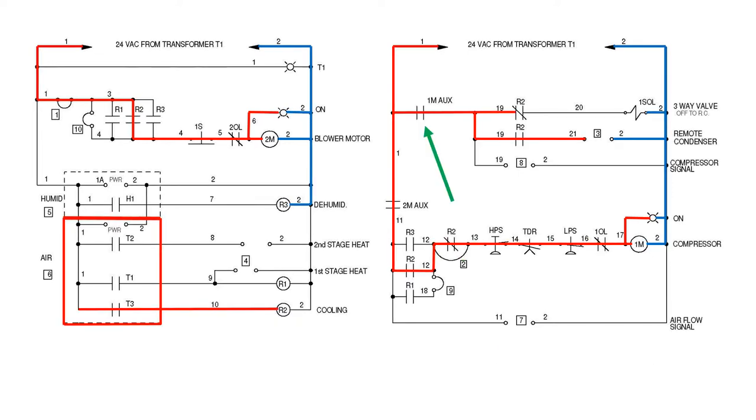The compressor contactor also has a 24 volt contact, here labeled 1MAUX, which now closes, de-energizing the three-way valve through R2 and sending the hot gas to an external condenser, which now starts. The room air is now leaving the dehumidifier cool and dry.